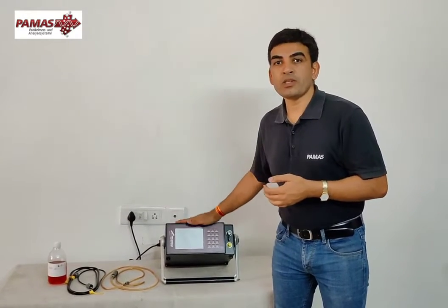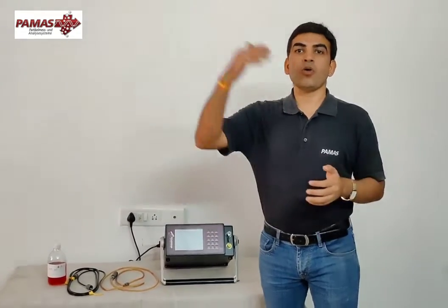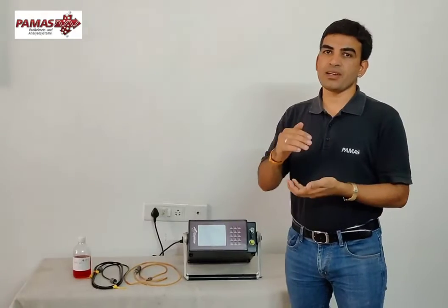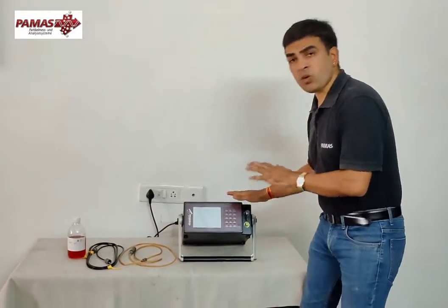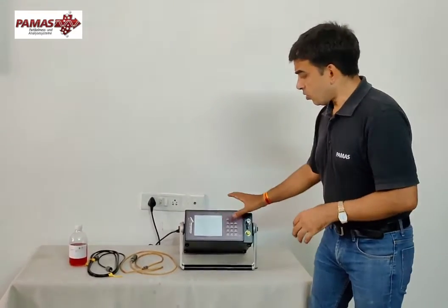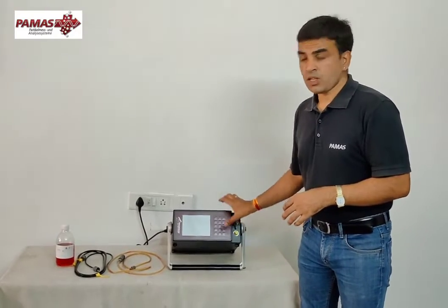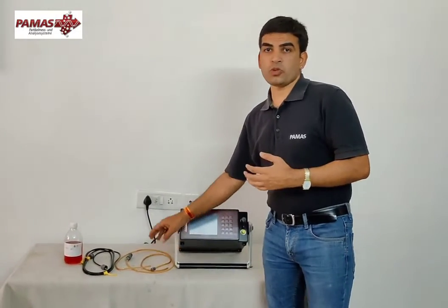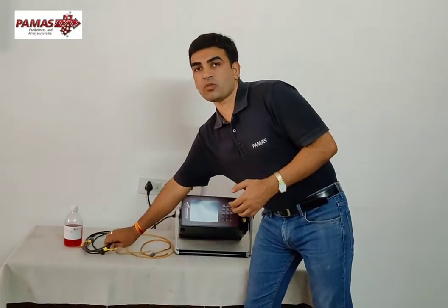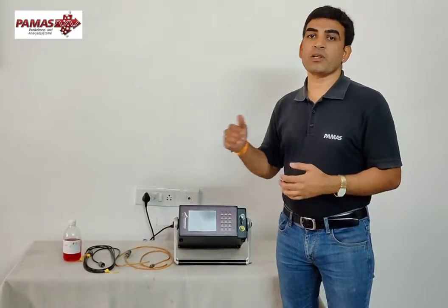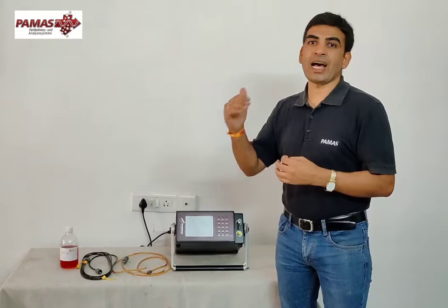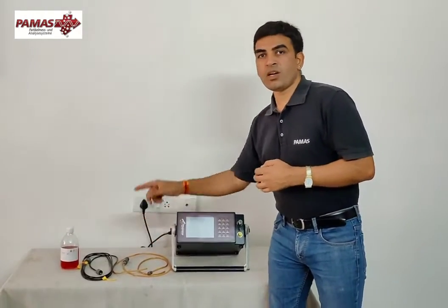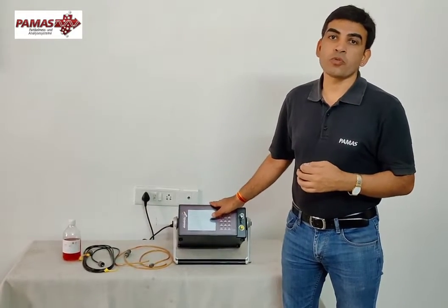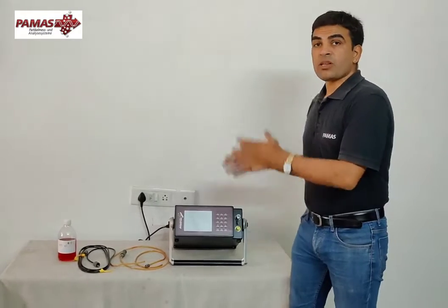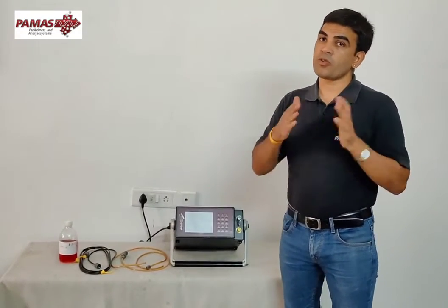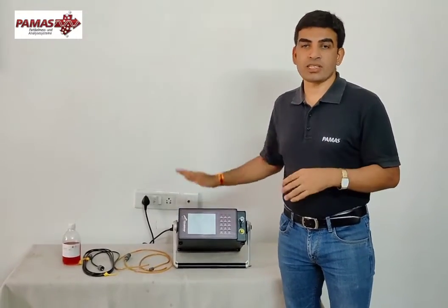You can use this instrument for batch measurement or online measurement. In a batch measurement, you can have your sample in a container or in a bottle. You need no additional accessories for that. Here on the bench you can see the complete set of the instrument. You just need 2 hoses for offline measurement, and you need 1 hose when you are using the system for online measurement. Online measurement means you simply connect the instrument to any pressurized system or any live hydraulic application with this mini mesh coupling. It will handle a pressure up to 420 bar. So for batch and online measurement, you can use this instrument from 0 to 420 bar. Any pressure it can handle.